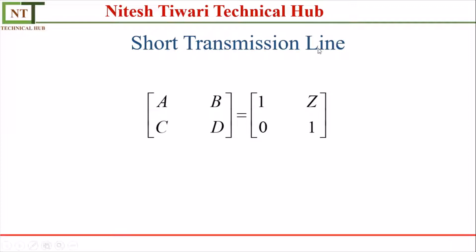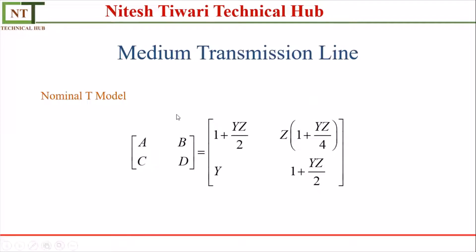For the short transmission line, the value of A is 1, B is Z, C is 0, and D is 1. This means we only need to compute the value of Z to calculate the ABCD parameters of the short transmission line. To compute Z, we need to know the resistance and inductance per kilometer.